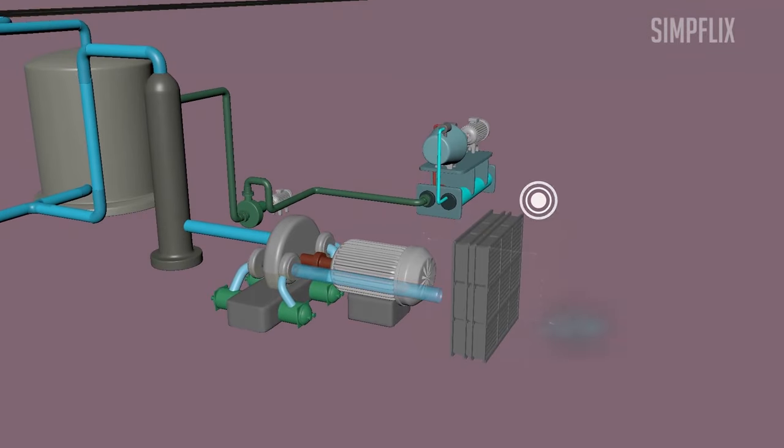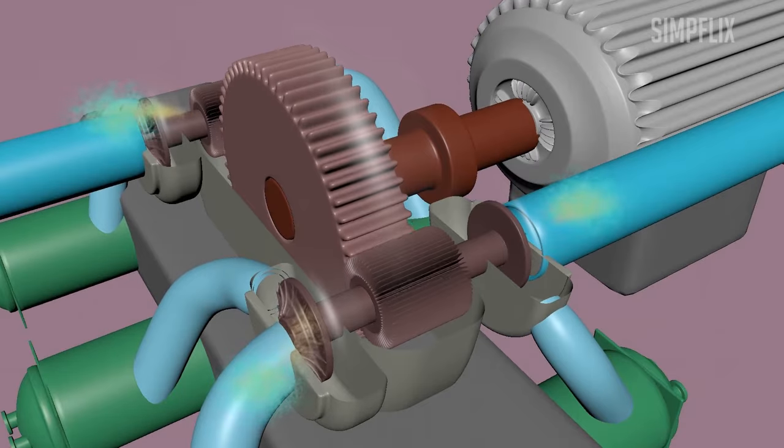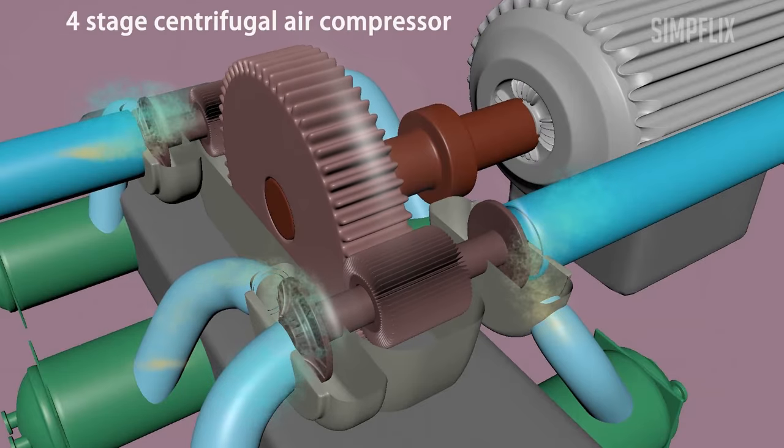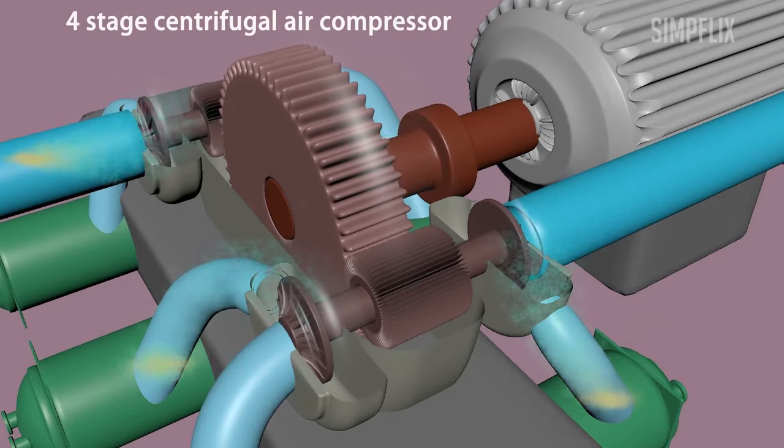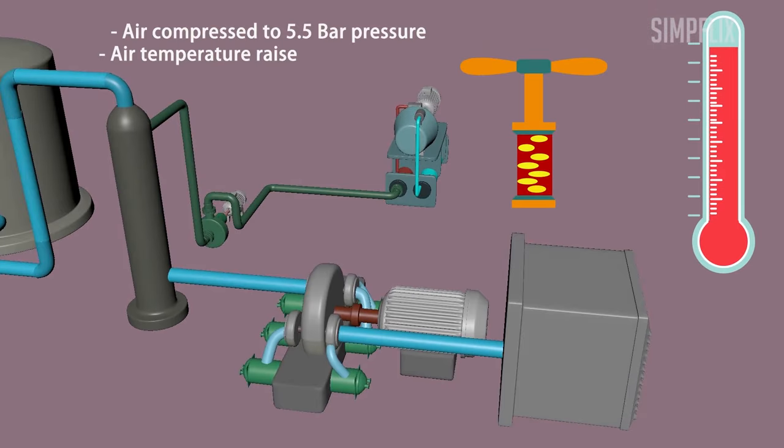First, air from the atmosphere is suctioned and filtered using filters to remove dust particles and other hard impurities. Then filtered air is compressed in a compressor up to 6 bar pressure to make the air flow from start to end of the process. If the air is compressed, then temperature will increase due to increase in kinetic energy of air molecules.